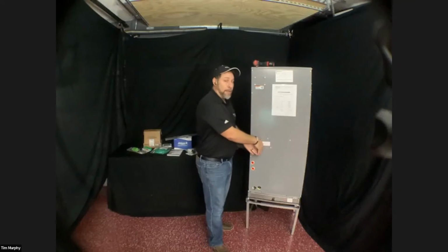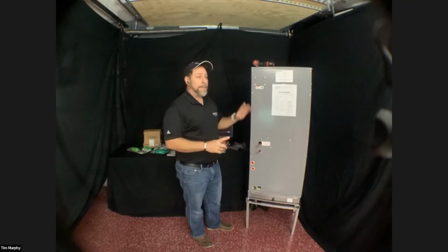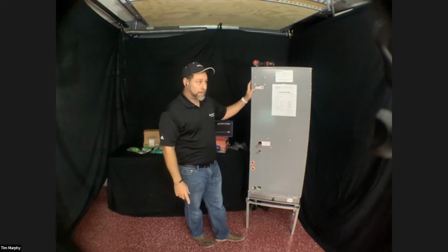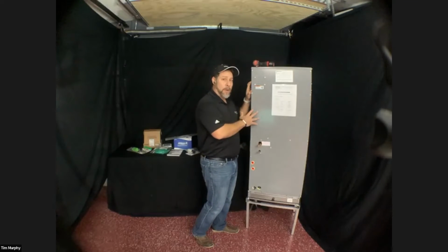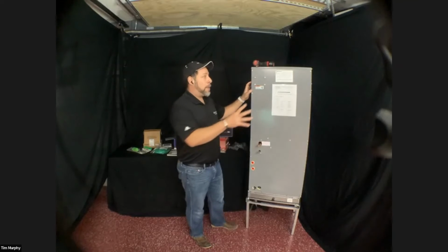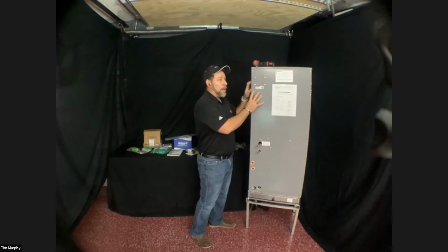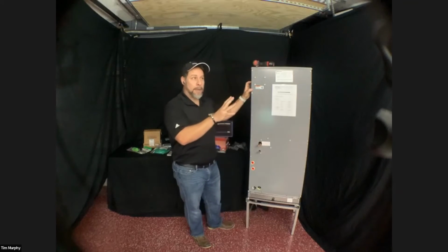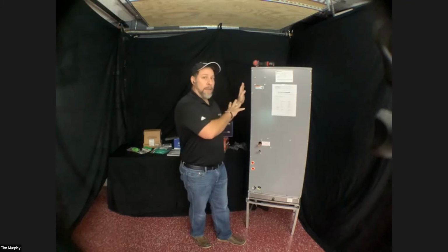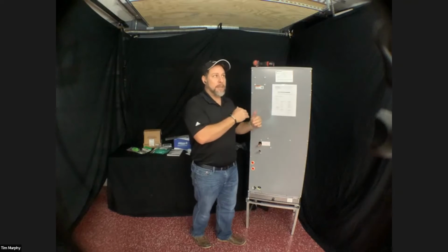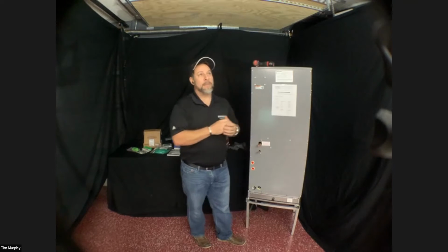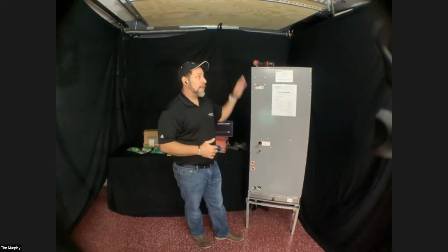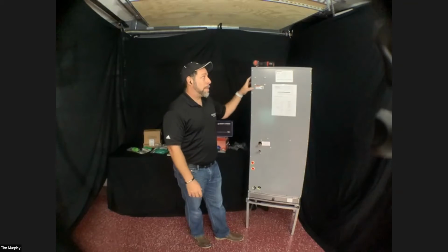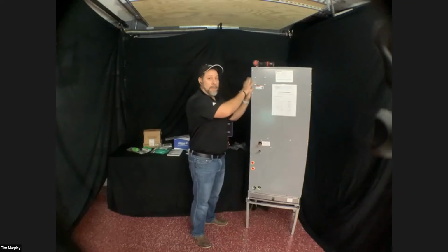But you're going to have to rerun the copper. You will have to power the air handler from the condenser, and you're going to have to run your communication wire as well. There are a couple of reasons why we power the air handler from the condenser. Will it work if you don't? Yes, it will work. But this is just something that's going to help prevent later nuisance calls that may or may not happen. Because I've already seen several jobs where they power this air handler off the same power that they powered the old air handler with.